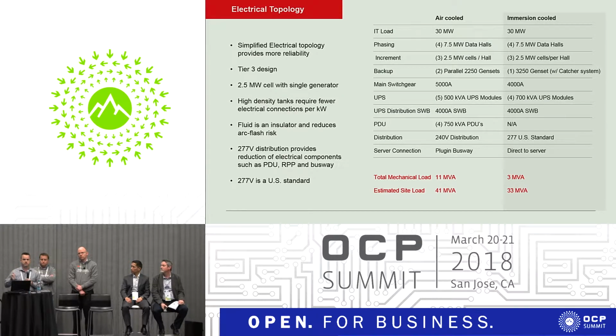The reason we actually show that is that because of the extreme densities that we're dealing with here, your mechanical systems need to be on UPS backup power. The IT equipment stays cooled so long as the liquid level in the tank is at or above the top of the circuit boards. If you have a power failure and you don't have water continuously moving through the cooling coils in your tanks, condensing that liquid back in, then your liquid level starts to drop. So this whole system was designed based on the need to put that mechanical infrastructure on UPS power and carry it through.